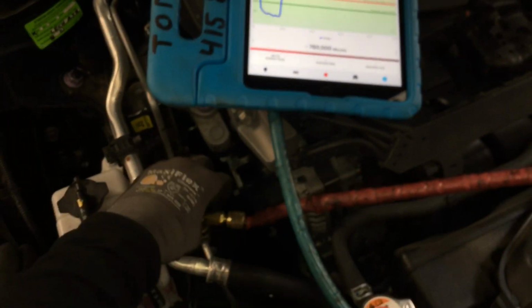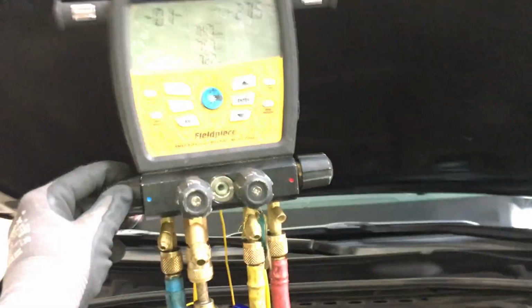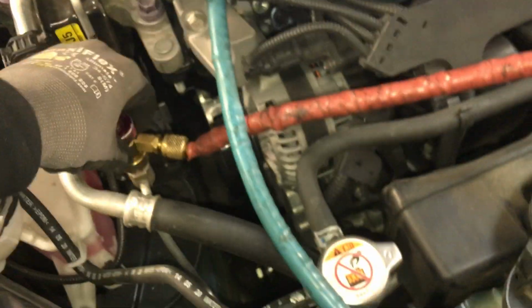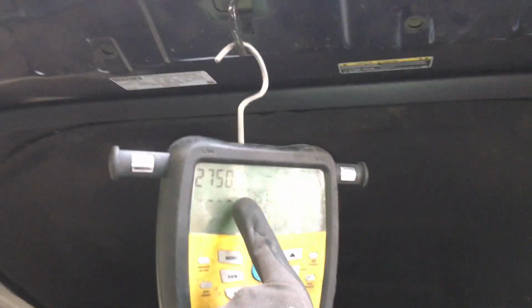And let's turn this down and see what happens. There we go. I just put that down. And that is open. And why am I not getting anything? Nothing's happening here. So am I having a problem? Did I not go down all the way? I have the vacuum source open. I'm dropping in microns here, but I'm not dropping in microns there. I have that open. Houston, do we have a problem?